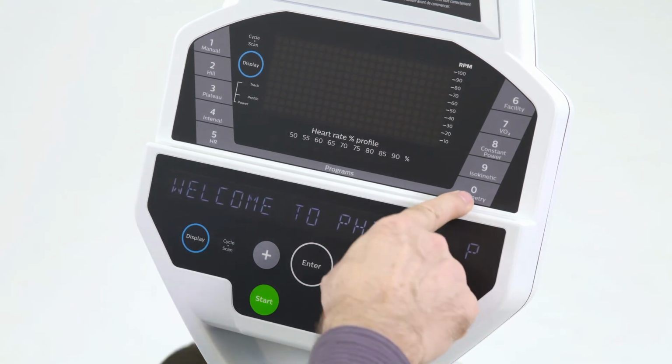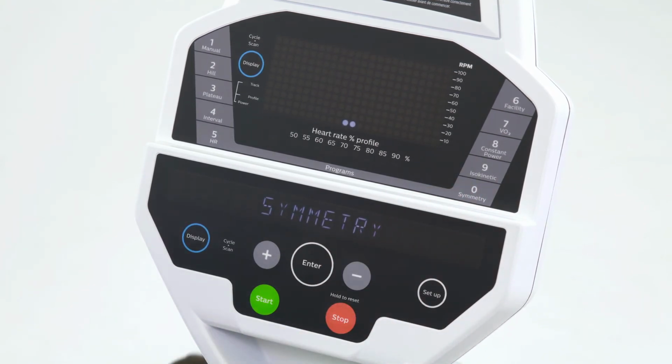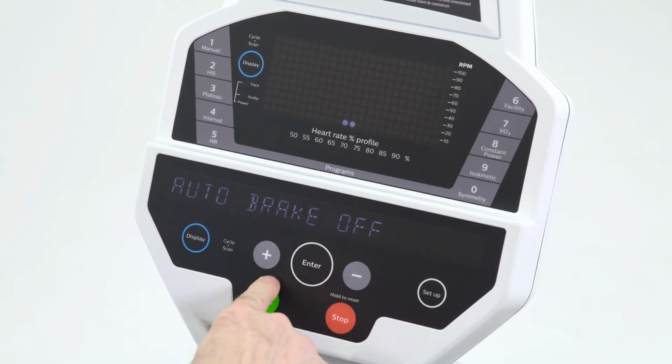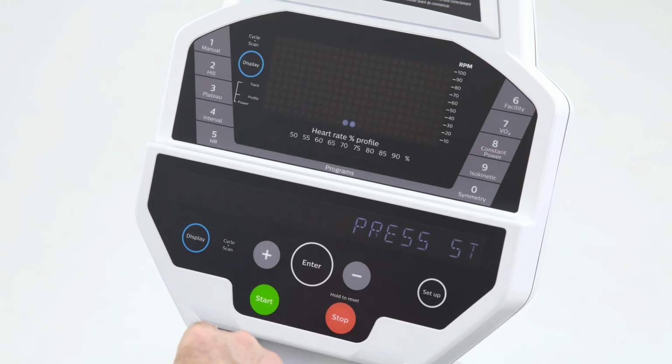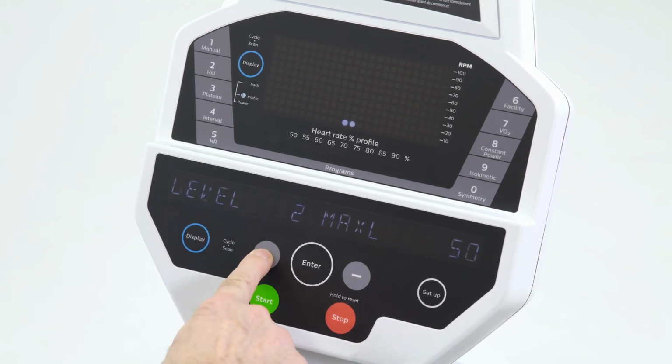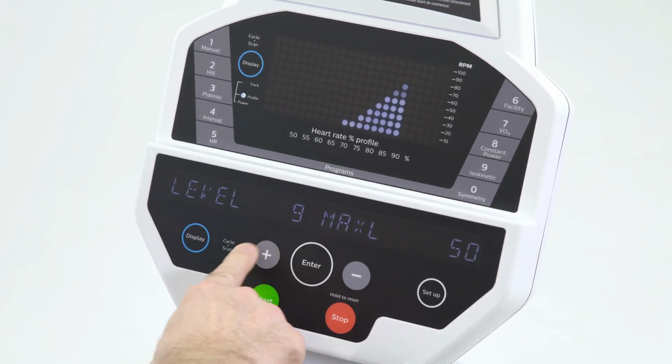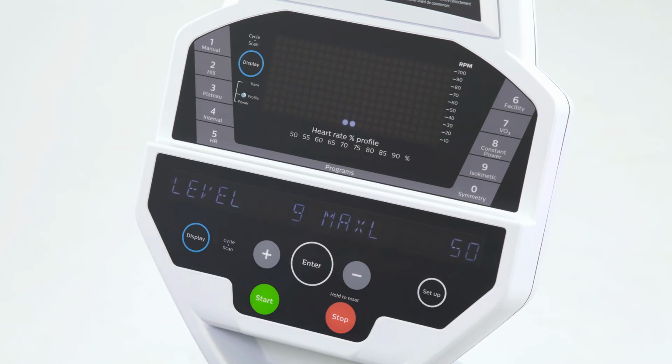In the console, we also have a symmetry program. When I press the symmetry program, the brake should be off in this program. We're going to be able to measure the patient's left versus right watts. And usually you have to have some resistance on the pedal.